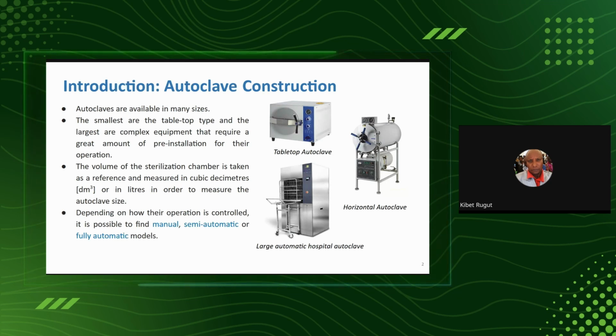So we have the three types that we commonly use: tabletop, a horizontal medium-sized autoclave, and then the large automatic autoclave. The large one sometimes may not necessarily be automatic. It is sometimes fully manual, where you use a timer when you have gotten your steam generated, set the goods in the sterilization chamber and open manually. Others are semi-automatic, where you have to intervene at some stages as an operator. And others are fully automatic. Once you set up a formula, you leave it running as long as there's electricity supply, and they are programmable and adjustable to the standards that are required.